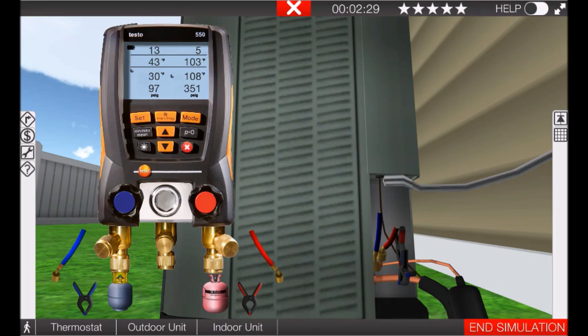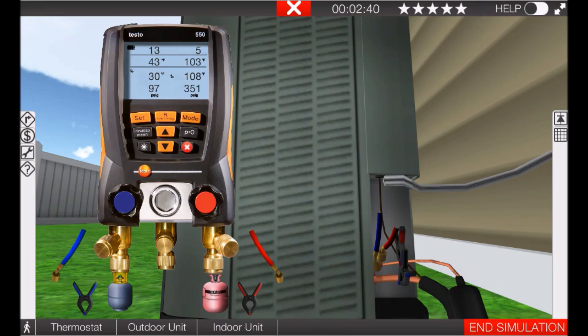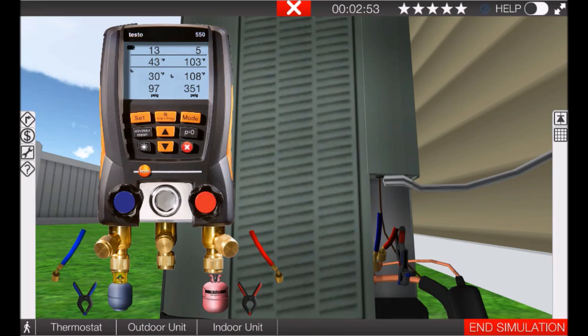So just remember those numbers: we have 97 psig on the low side, 351 on the high, 30 degrees saturation temperature, 108 saturation temperature for the high side, the line set temperatures 43 degrees on the suction, high side is 103, with 13 degrees of superheat and 5 degrees of subcooling.